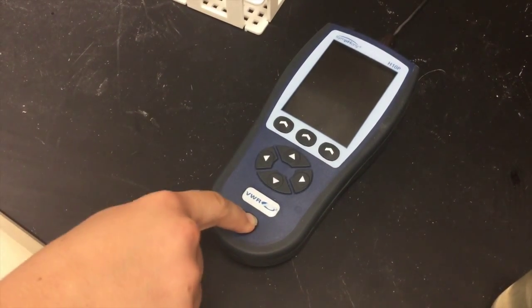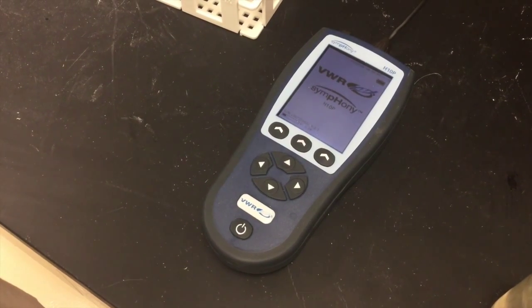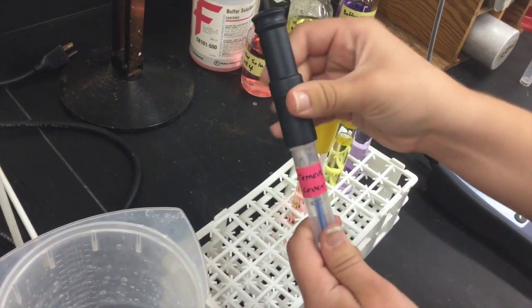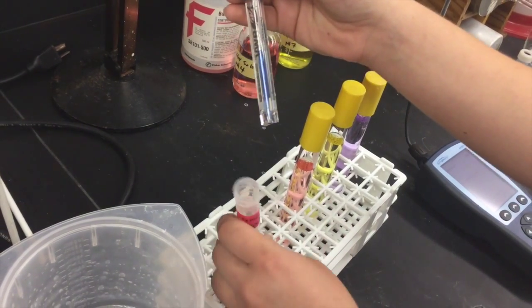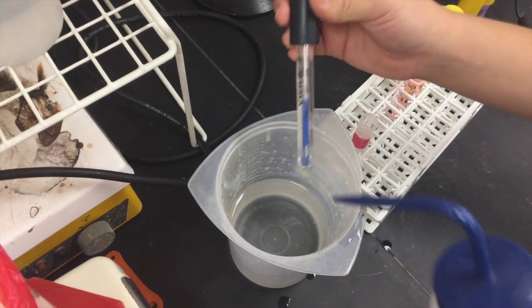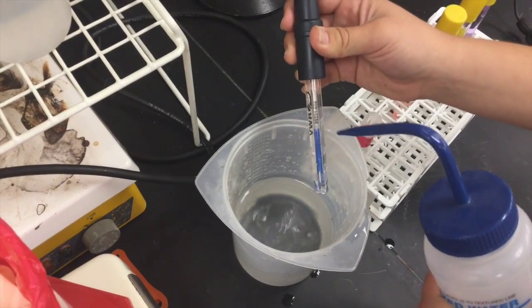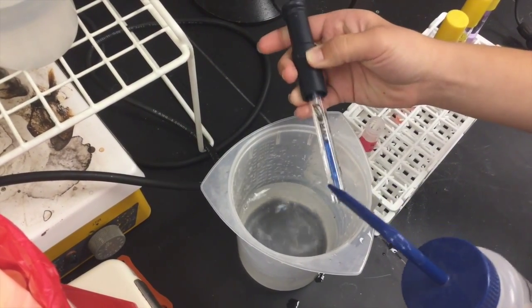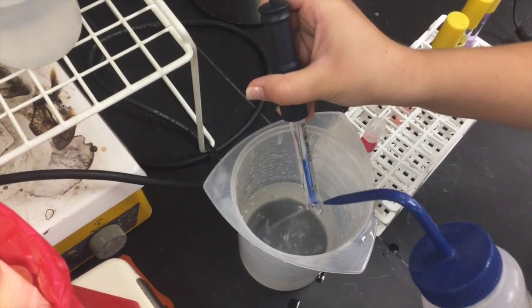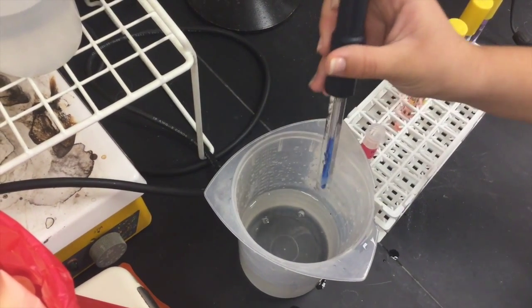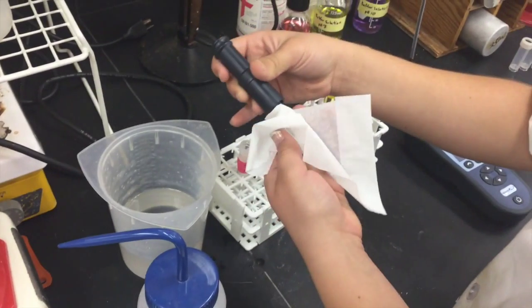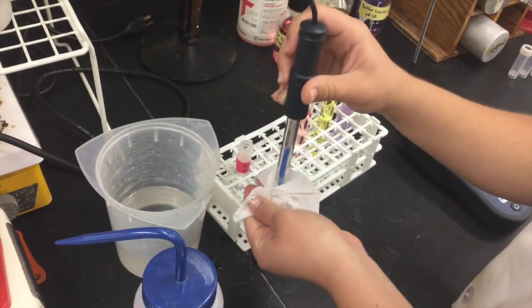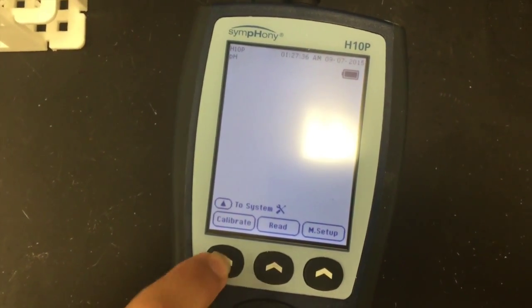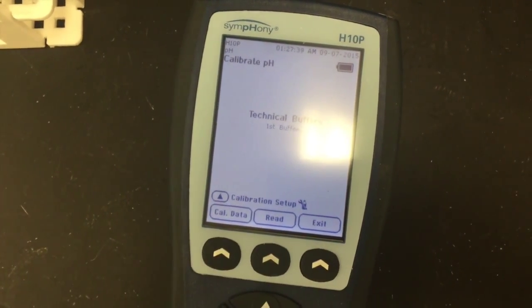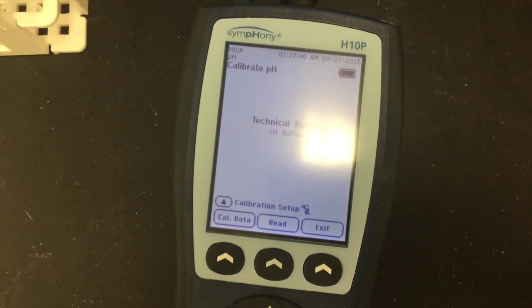First, turn on the pH meter by pressing the power button. Then carefully unscrew the cap from the probe, being careful not to spill any of the liquid inside. Use your squirt bottle filled with deionized water to gently clean off the probe. Make sure to be extra careful when cleaning off the bottom of the probe. Then gently wipe off the excess water using a Kim wipe. Once the pH meter has finished powering on, press the Calibrate button. At this point, it will direct you to test the first calibration buffer.